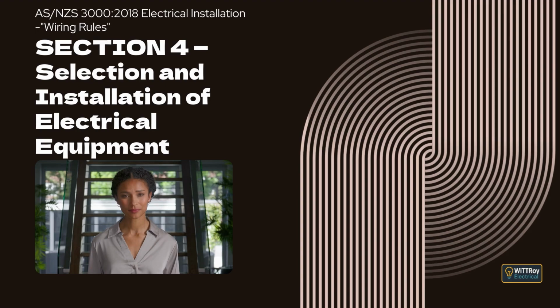Clause 4.3.2.1, General. This clause explains that installation wiring may be directly connected to terminals provided on the equipment for that purpose. Clause 4.3.2.2, Installation coupler. This clause explains that an installation coupler meeting ASNZS 61535 is suitable for connecting cables, including flexible and rigid types. It explains that installation couplers are intended for permanent connections between wiring sections and are treated like junction boxes, and that they require deliberate action to disconnect and are not intended to be used under load or as socket outlets.